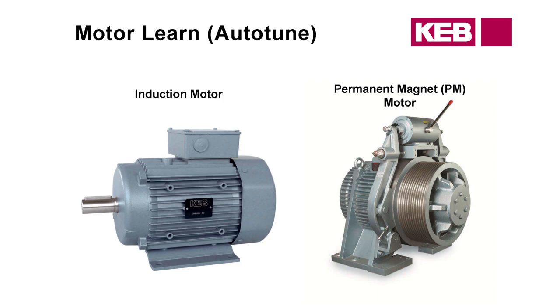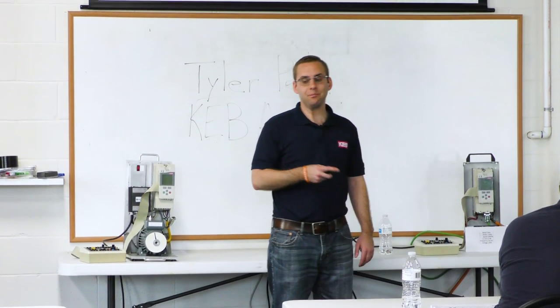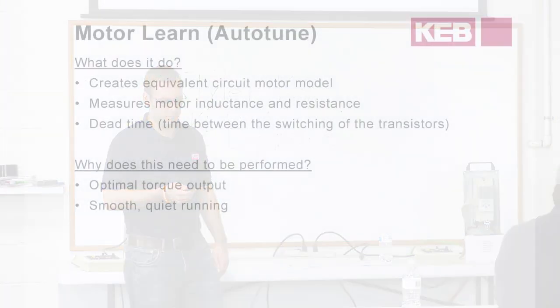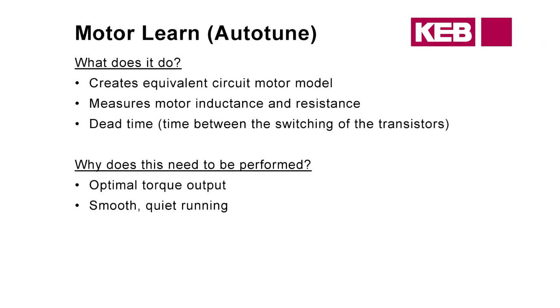For permanent magnet machines, the motor learn is required. If you don't do it, the motor will not turn at all. The data measured during the auto-tune will be used for the encoder learn, so we need to do a motor learn with the correct motor data to have the correct encoder position. What it measures is the motor inductance and resistance, and what it does with that is create an equivalent circuit model internal to the drive, which gets fed into the feedback loop during closed loop operation.